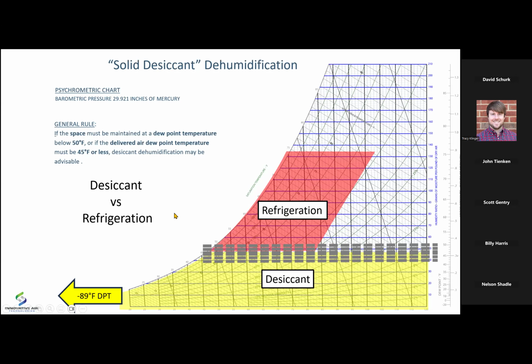If the space needs to be maintained at a dew point temperature less than 50, or the delivered air dew point to the space must be 45 degrees Fahrenheit dew point temperature or less, and that's right about in the middle here where you see the yellow line begin. If it's either of those or more stringent, you should probably be thinking about desiccant dehumidification. And in fact, if you're much more stringent down here in the yellow area and two psychrometric charts off to the left, down to about negative 90 degree dew point temperatures, solid desiccant's your only solution. It's the only thing that'll work, right?